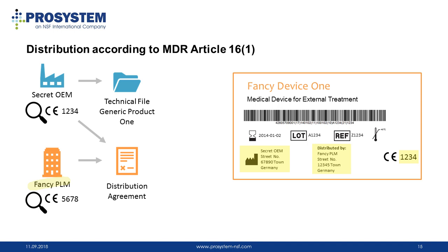You can, of course, also label the PLM as a distributor. You have to clearly state who is the legal manufacturer, which is usually done by this factory symbol.